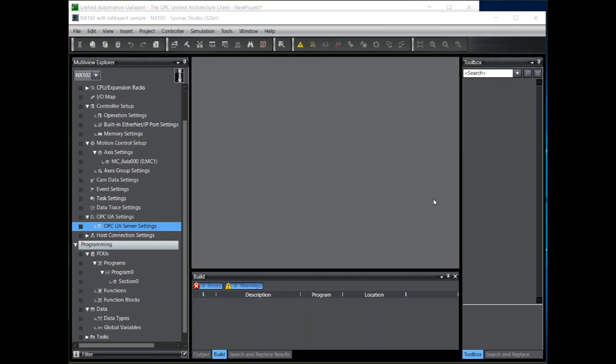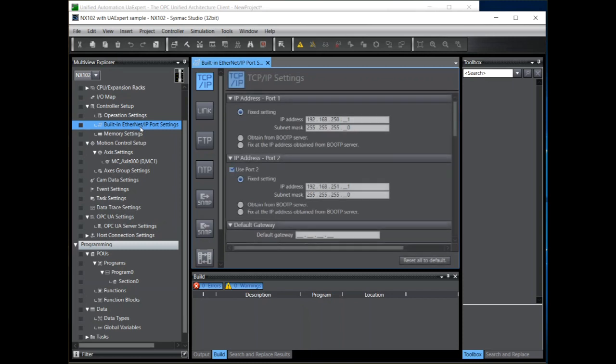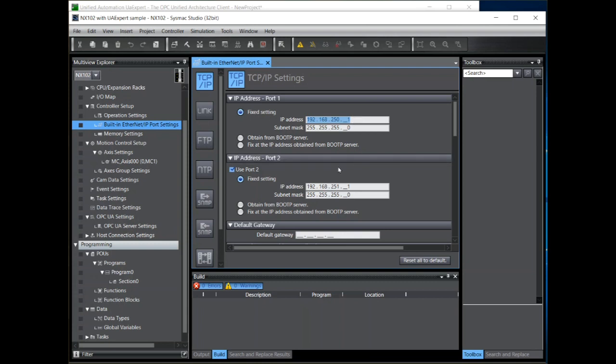Note that the OPC UA function only works with Ethernet IP port 1 on the NX102. If we check the settings here for the Ethernet port, notice the IP address I'm using. This is the default IP address for port 1 of the NX102. The OPC UA server function cannot be used for port 2.